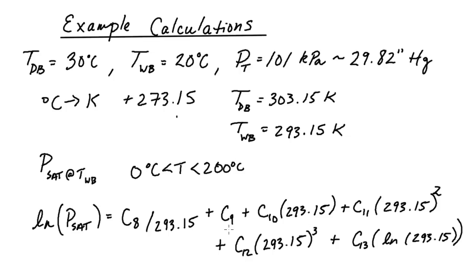There's the equation with all these C terms - C8, C9, C10, C11, C12, C13 - they're all constants that are defined. We have a temperature term here, the wet bulb temperature in Kelvin. These are all in absolute temperature divided by T to various powers: T, T squared, T cubed, and then the natural log of T all times these constants. That's the natural log of the saturation pressure at that given temperature.